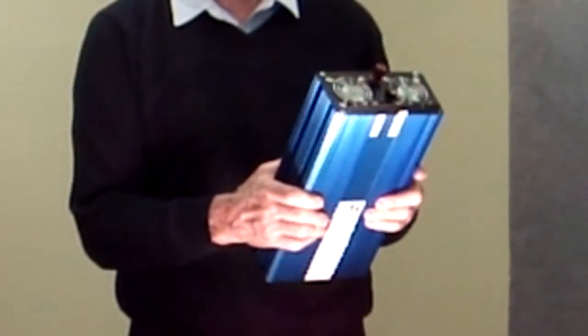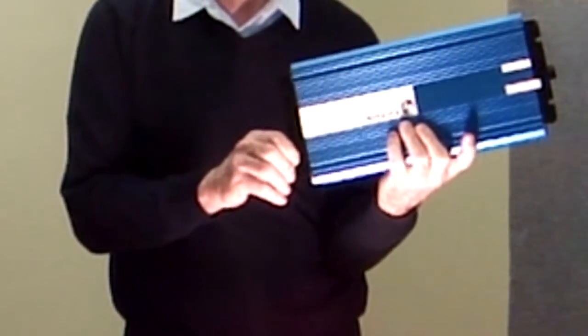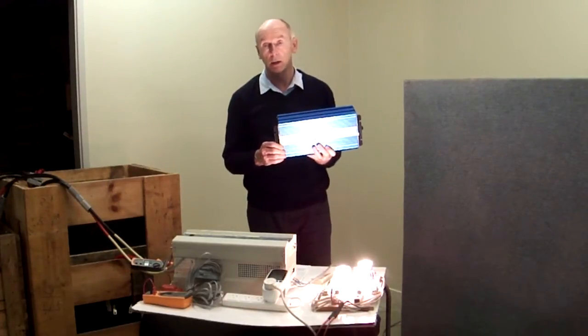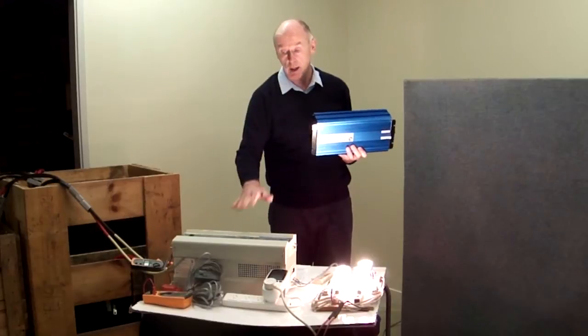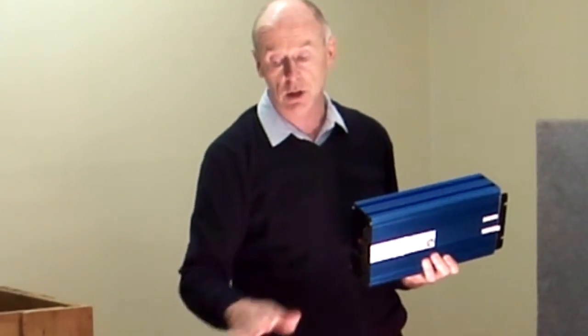The high frequency inverter will only handle approximately two times rated current, so this would only handle 3,000 watts for maybe 0.2 of a second. 0.2 of a second compared to 20 seconds. This is only two times rated power as against three times rated power.